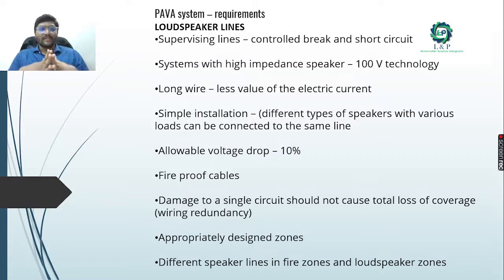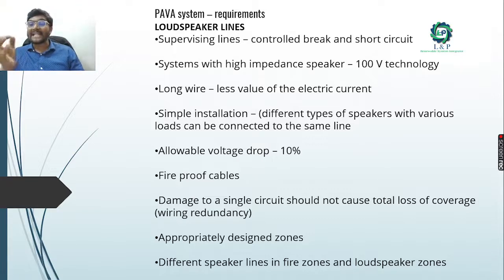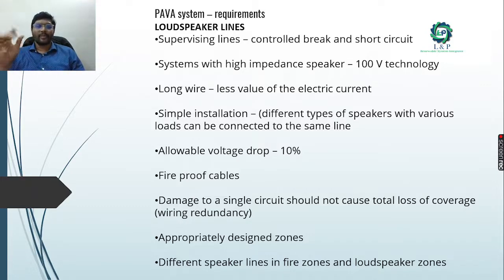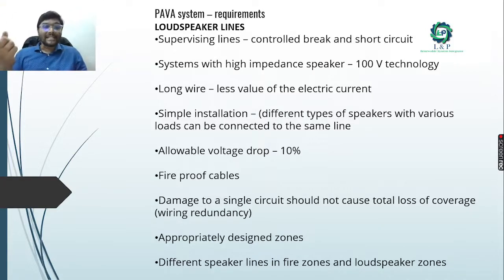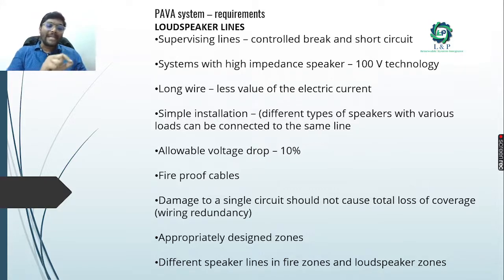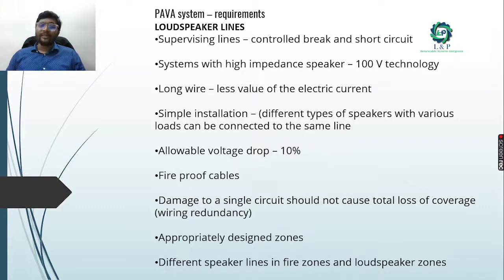The behavior requirements include: loudspeaker lines should be controlled for break and short circuit; high impedance speakers using 100-volt technology should be used; long wire with low electrical current values; simple installation; maximum allowable voltage drop of 10%; and fire-rated, fireproof cables must be used. If damage occurs to a single circuit, it should not affect other circuits - wiring redundancy is required. Zones must be appropriately designed for the evacuation process.